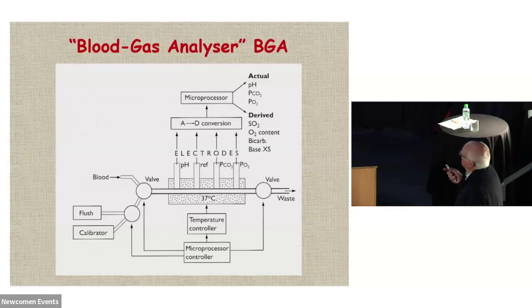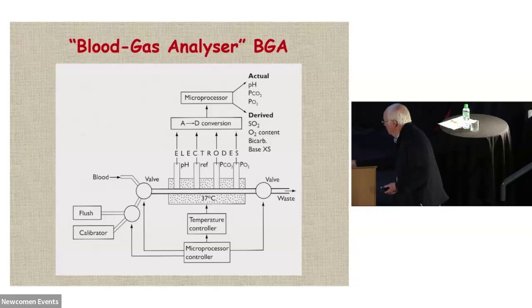In this system, this derived bit here is calibrated and calculated as a series of algorithms, and it's only accurate really for human adult HbA, in other words, normal adult hemoglobin. But if it goes through a separate spectrophotometer bit here, you can get the true value. And then it's sucked out and it's to waste. But this is taking blood samples out of a patient, usually arterial samples.